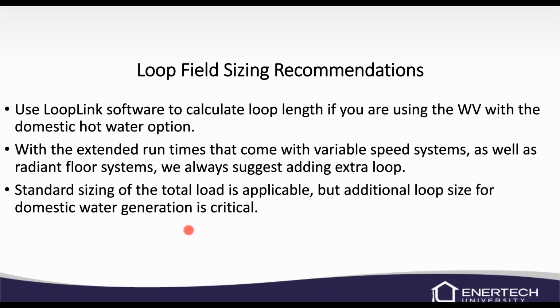On the loop field, you can use the LoopLink software to calculate the loop length. If you are using it with domestic hot water, we have a little bit longer run times, so we need to probably add a little bit of extra loop. Now you can do standard sizing of the total load, but additional loop size for the domestic hot water is necessary and is critical. So you can check out the LoopLink software. If you still have questions, definitely give me a call and we can discuss how much we think you really need to add. A lot of times if you've got a vertical loop, they're just going to add one more well, or if you've got a horizontal loop, they're going to put in one more trench, basically another ton of capacity or so.